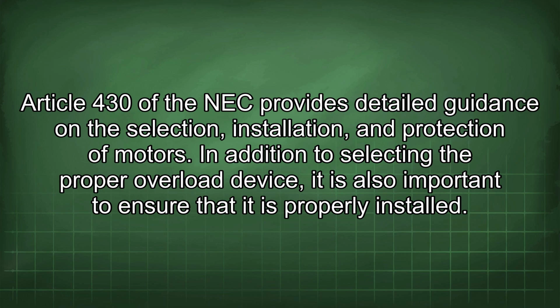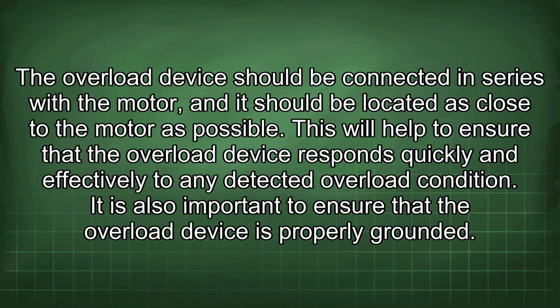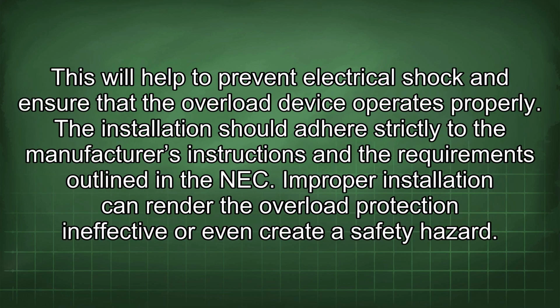In addition to selecting the proper overload device, it is also important to ensure that it is properly installed. The overload device should be connected in series with the motor, and it should be located as close to the motor as possible. This will help to ensure that the overload device responds quickly and effectively to any detected overload condition. It is also important to ensure that the overload device is properly grounded. This will help to prevent electrical shock and ensure that the overload device operates properly.